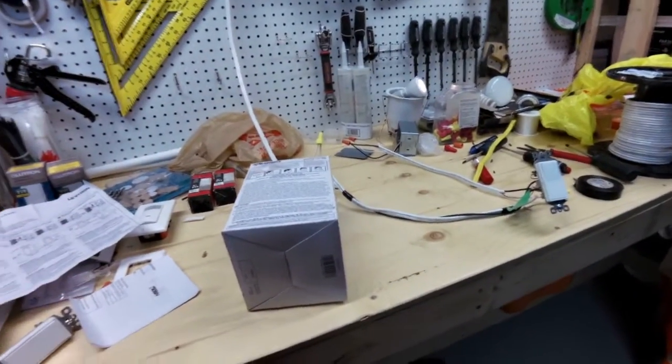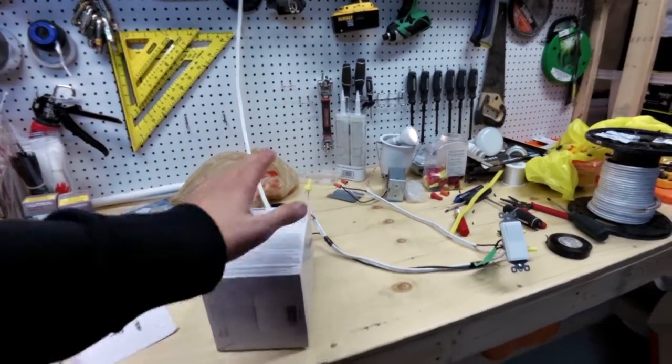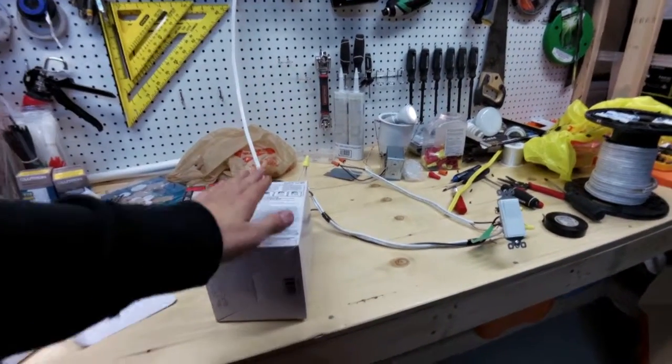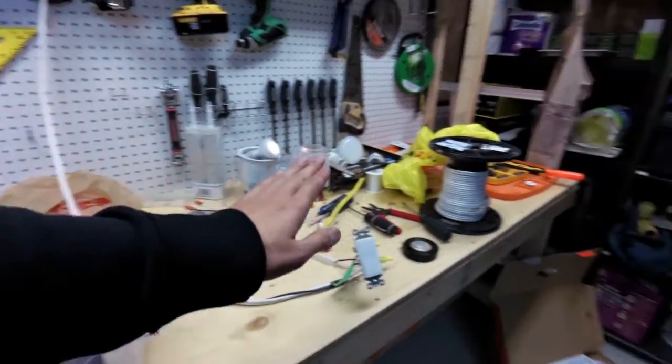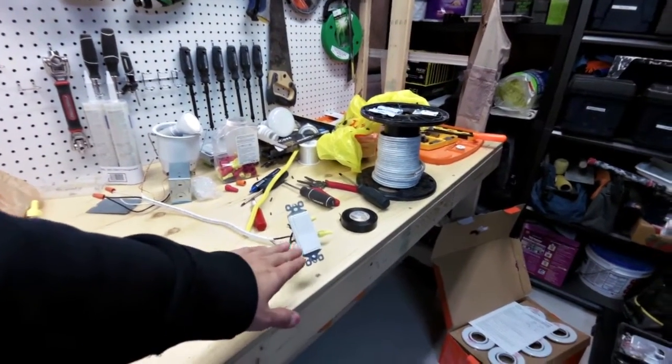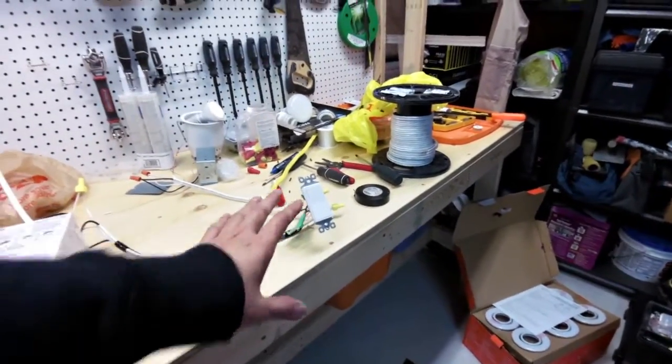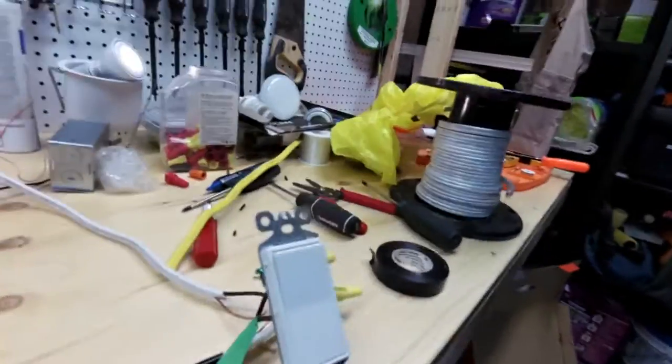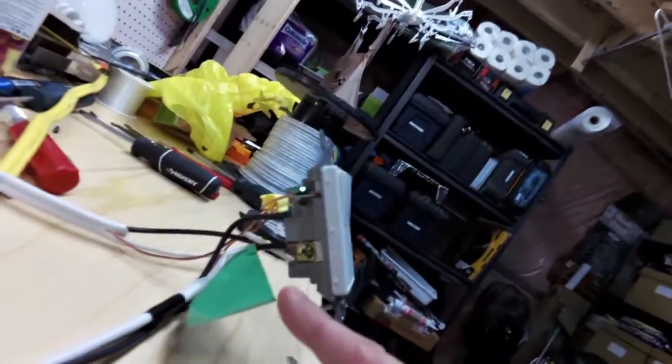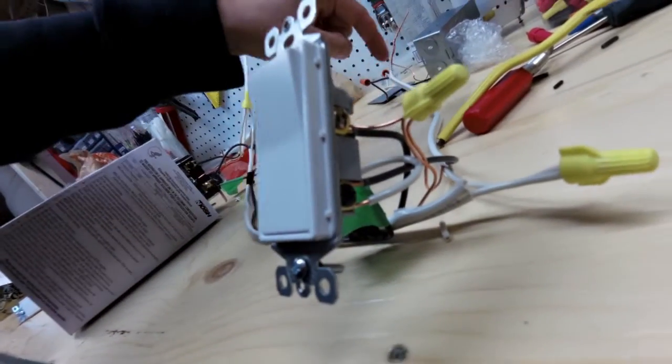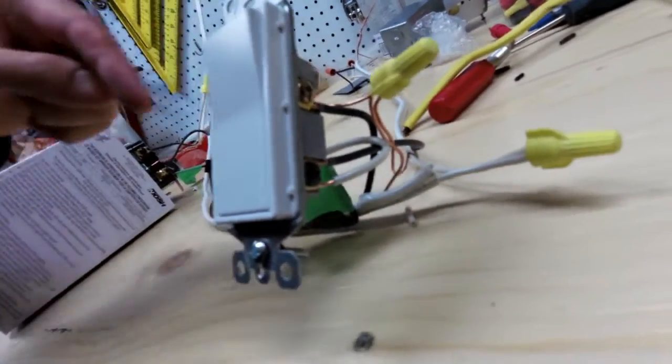However, the one thing that you really need to know is that not only will you have to change the light switch on one side, you have to make a very small change on the other side, even though there's nothing new here. What you need to do is short out the red cable to the load block cable. You're going to have to short that out.